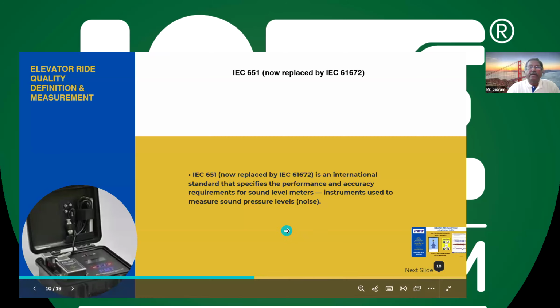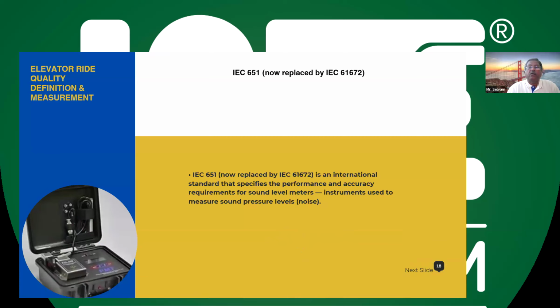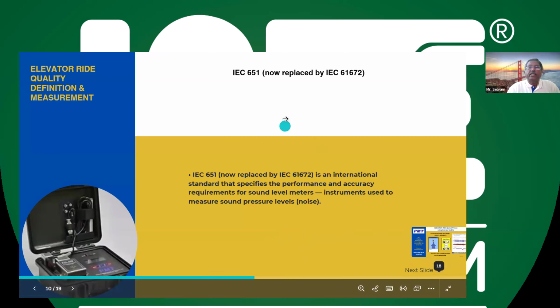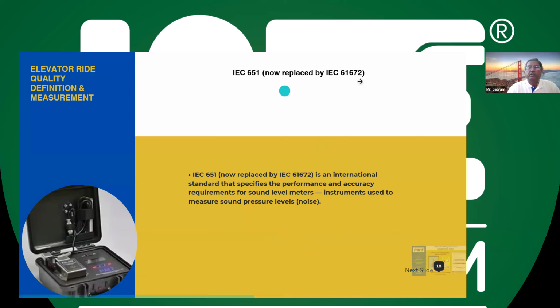So there is a mic provided for such an instrument. If you see here, it is used for measuring the noise inside the car during the ride. So that standard is governed by IEC 651. Now it is replaced by 61672. I think more or less the same. So these are the three standards which are used: ISO 2631, ISO 8041, IEC 61672. These three standards are helping to formulate the specification, the requirements for the ISO 8100.